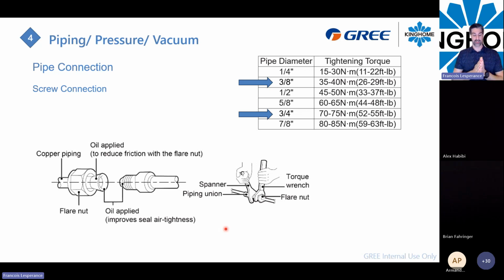So anyways, if your piping is attached too tight on the wall or through the wall inside the house, and there's no place for the piping to move properly to take that expansion, well, your flare connection will take it, and maybe in a year or two that will create a leak. Even if the torque is good and the flare is perfect, it can create a leak because of the expansion and the contraction of the copper.